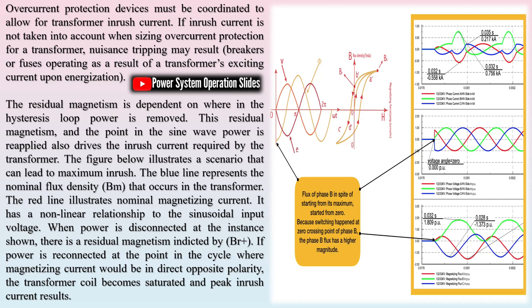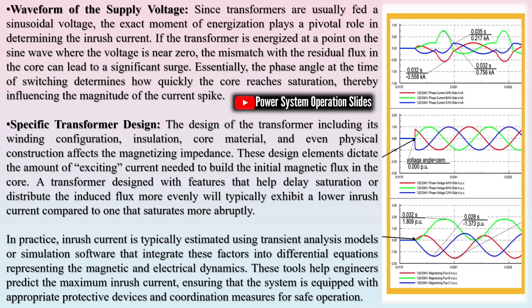When the core is driven into magnetic saturation, its effective permeability drops, causing a dramatic increase in the current drawn. Therefore, understanding the hysteresis or saturation characteristics of the core is critical, as these details determine how far the core can be pushed before the magnetization and thus the current spikes.